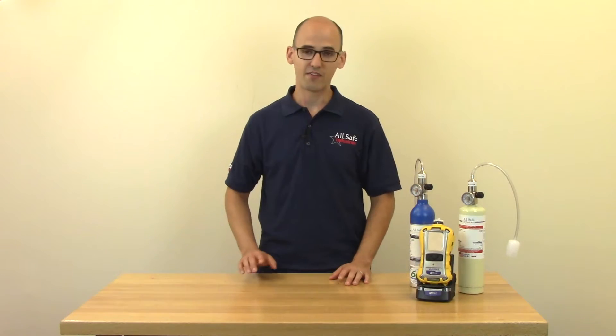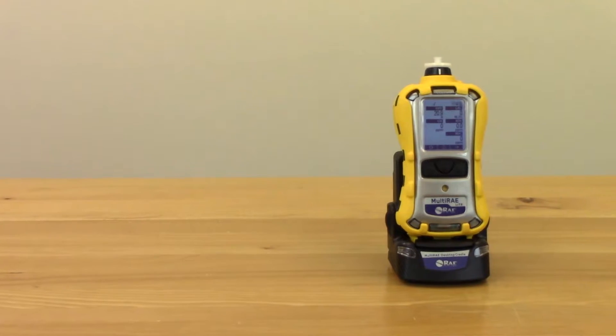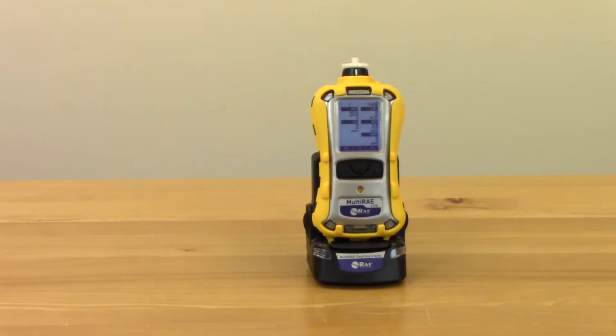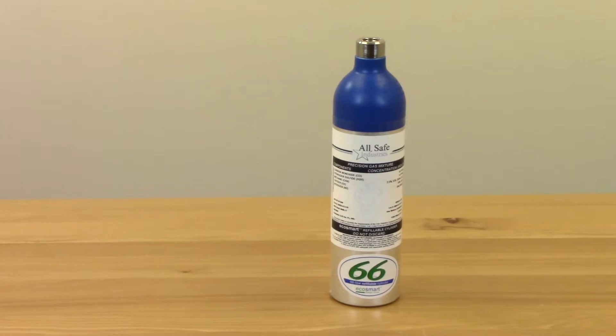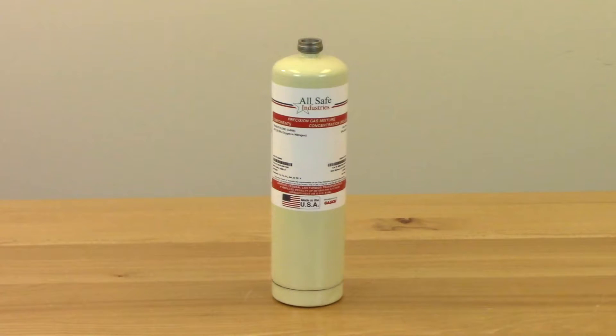First things first, let's make sure you have all the essentials. Of course, you'll need your MultiRAE. I have a standard config MultiRAE light here, but the calibration procedure will be the same across the MultiRAE family. You'll also need calibration gas. Since we are calibrating a standard MultiRAE light, we have a cylinder of four gas mix and some 100 ppm isobutylene for the PID.